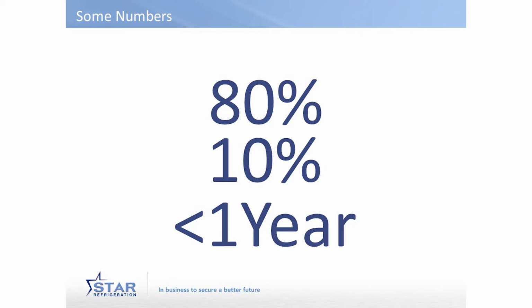No? 80% is roughly the amount of the energy that is used in the compressor of the refrigeration. We talk about the compressor as being the heart of the system. In a cold store, it might even be higher. It might be as high as 90%. In a chill store or a water chiller, probably more like 80%.